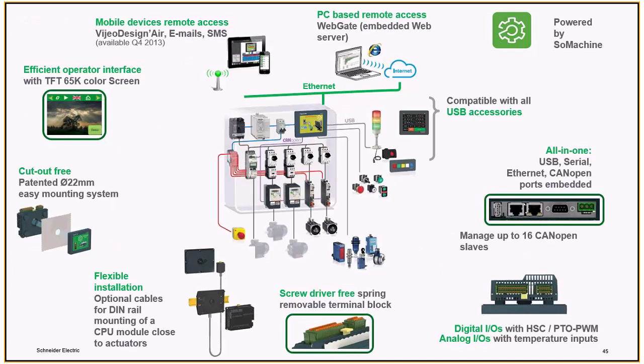Once there's a problem, I'll give an SMS alert to the first maintenance engineer, and if he's not able to resolve the issue, I can alert the manager, and if that's not acknowledged, next morning I can alert the plant head. So this hierarchy based alert system can be configured with this offer. On top of that, with the Ethernet port, I can connect to a mobile app, available on the Google Play Store, and go online with my HMI screen directly through the mobile app.